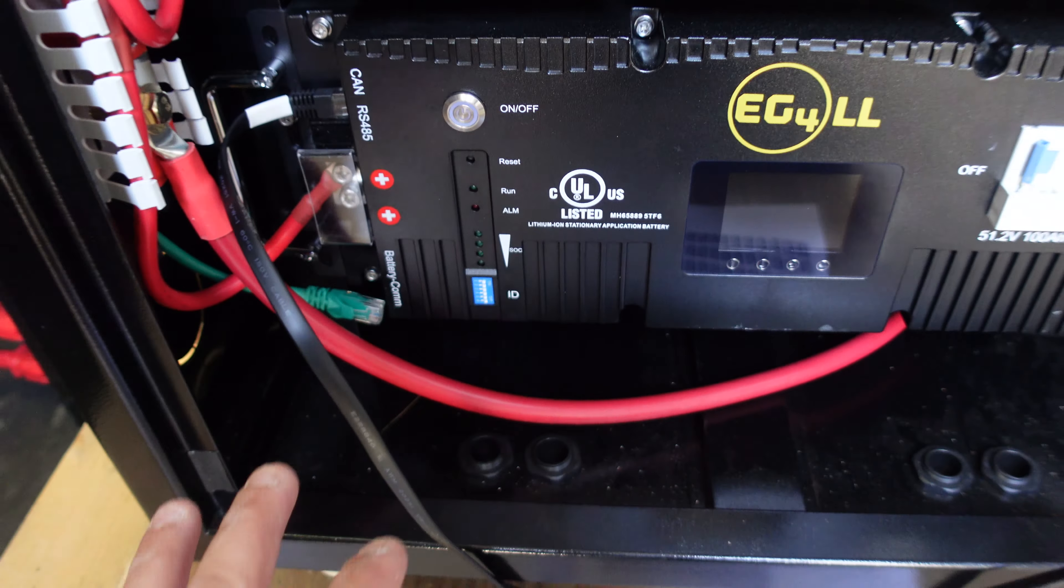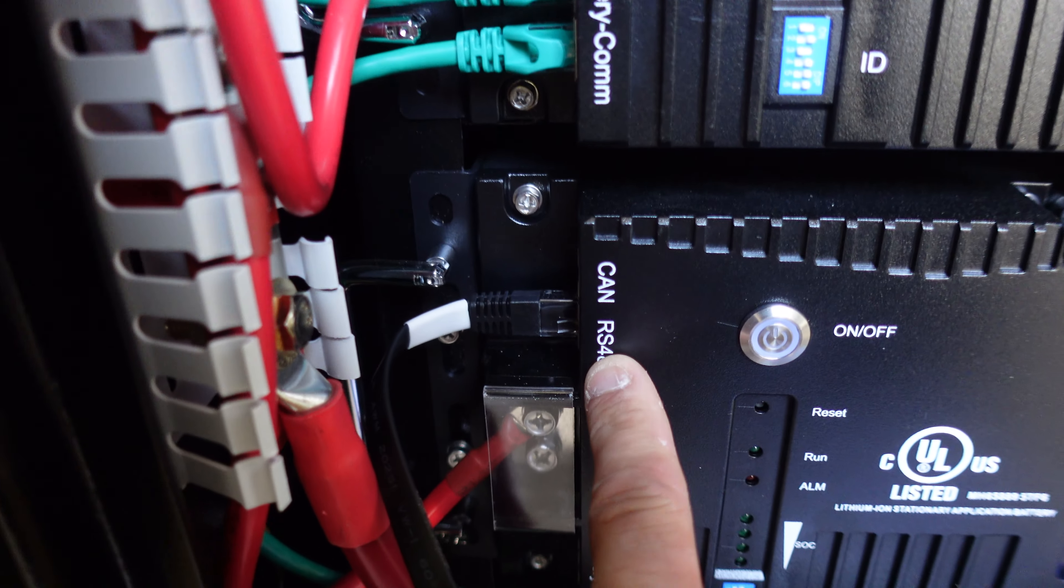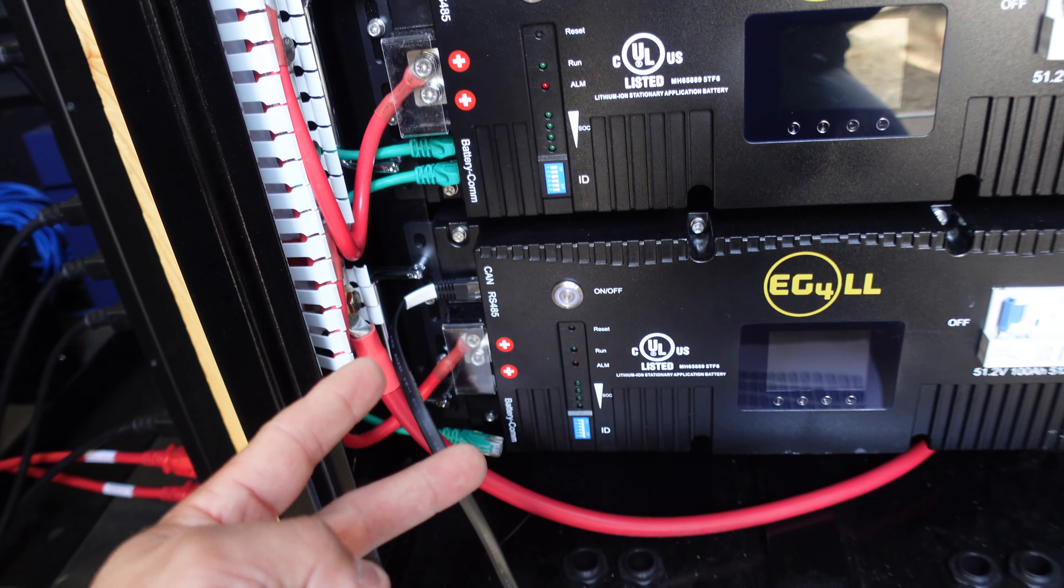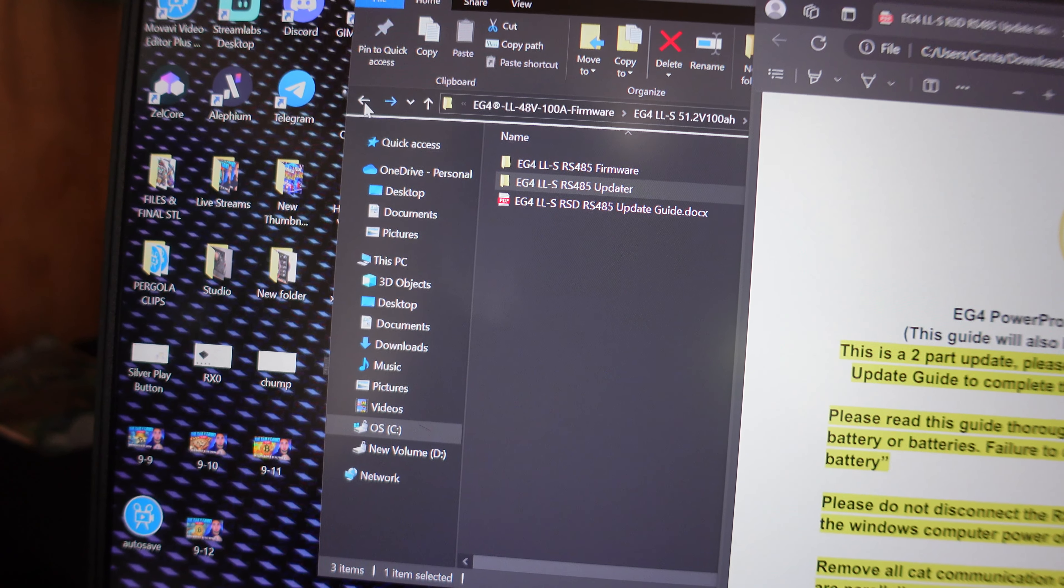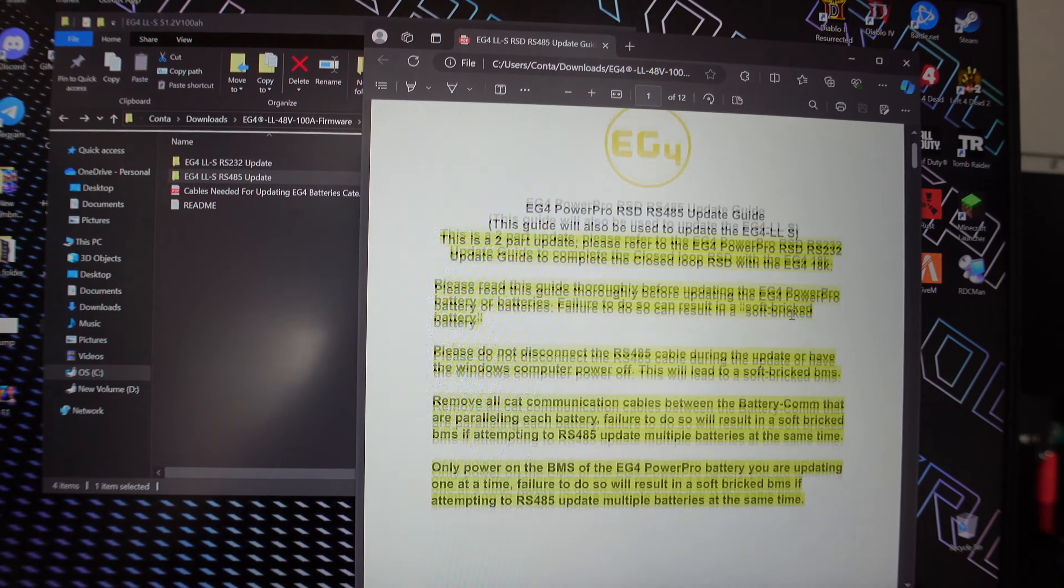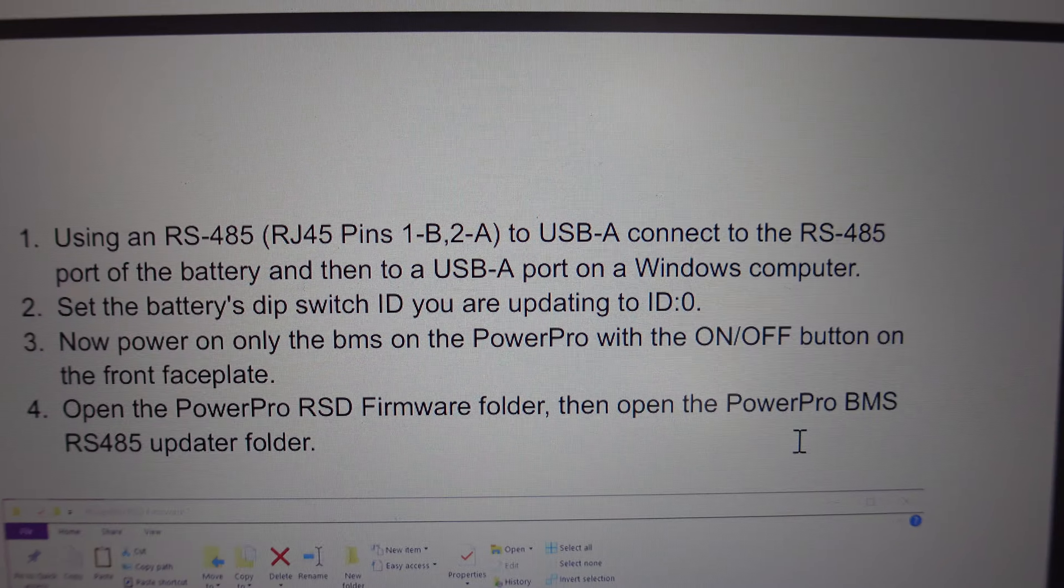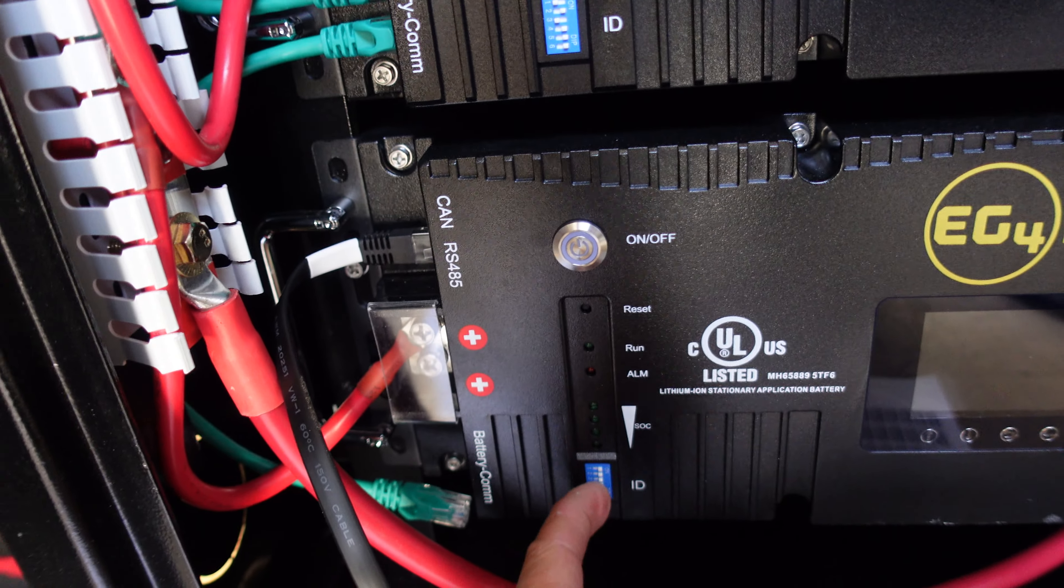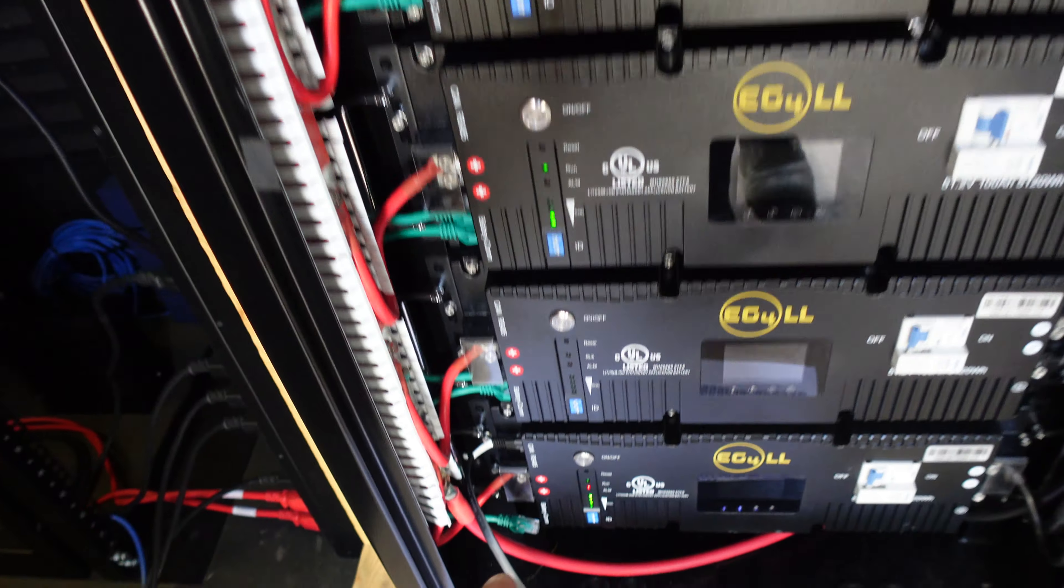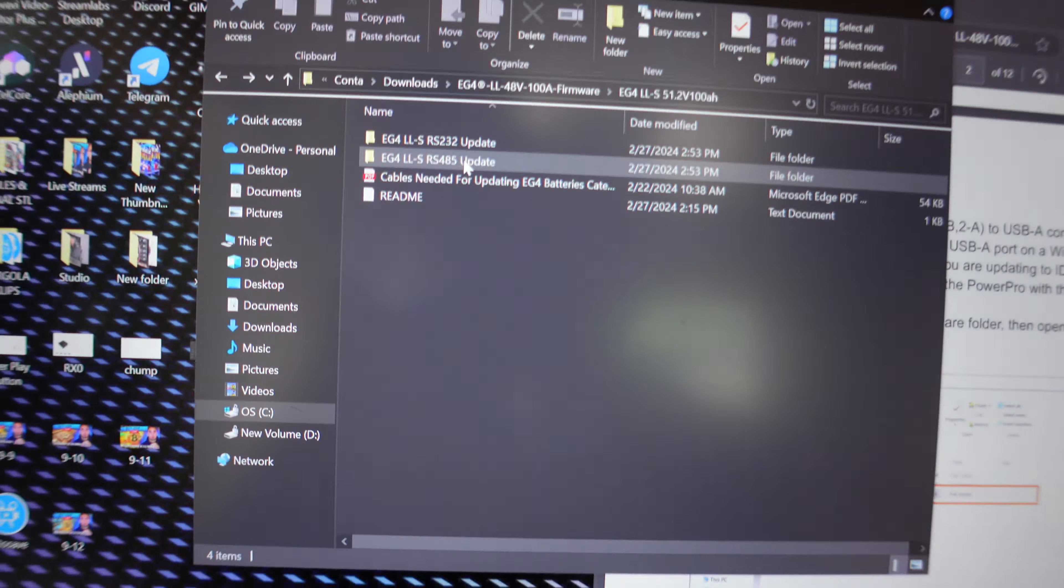So thankfully, my rep just got back to me. That worked perfectly fine, I turned it back on and checked, but you have to update the RS-485 one also. He said tech support said to make sure you do both. So we got to follow the next file inside this thing. Again, remember I said there is both here inside this folder - the RS-232 and the RS-485. So it's just a little bit different, but pretty much the same stuff. Make sure you don't power down the BMS, all that. But it says using the RS-485, make sure you connect it to the RS-485 port on the battery. So that's what we did. Right here, we got ID zero, and now I can turn this guy on. And we actually disconnected all the other communication ports.